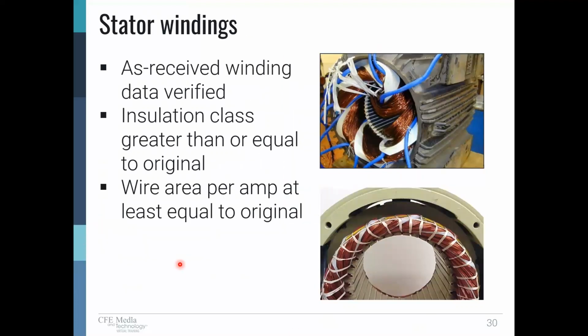Stator windings, the as received winding data is verified, and we'll show something on the next slide about that. The insulation class, thermal capability equal to or greater than the original. So if it was 130 degrees C class B winding by manufacturer's design, the service center is probably going to go back with 180 degrees C class H design. The wire area per amp is at least equal to the original. In other words, we're putting in the same size wire so we don't increase the resistance losses.